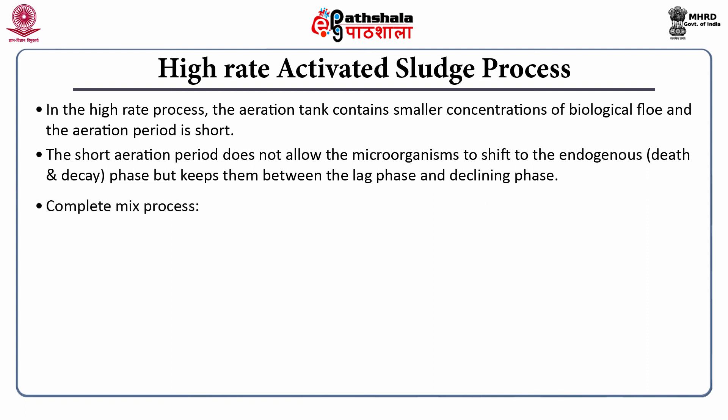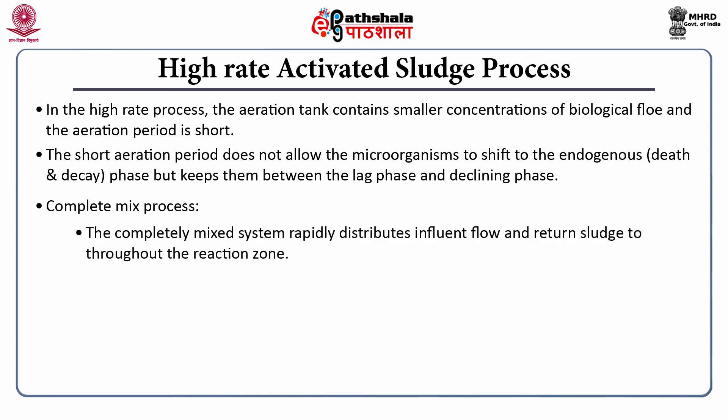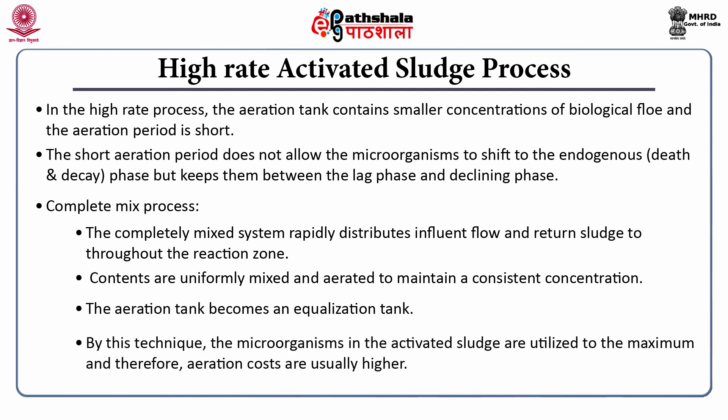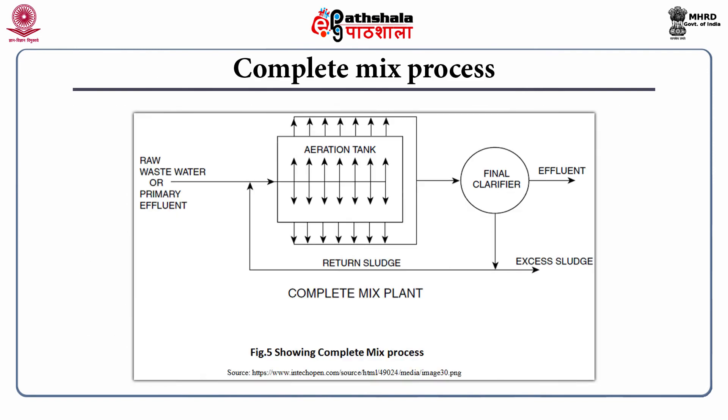Another variation is the complete mix process. The completely mixed system rapidly distributes influent flow and return sludge throughout the reaction zone. Contents are uniformly mixed and aerated to maintain a consistent concentration, and the aeration tank acts as an equalization tank. By this technique, the microorganisms in the activated sludge are utilized to the maximum, and therefore aeration costs are usually higher. This figure shows the complete mix process.